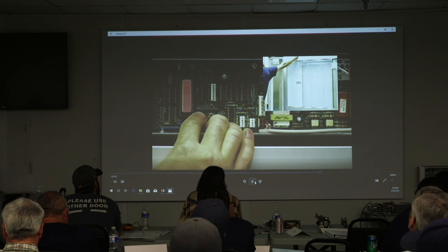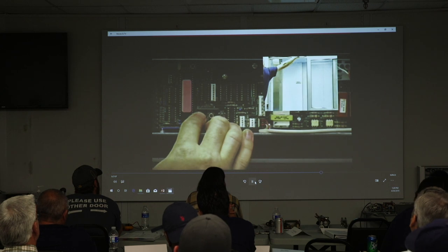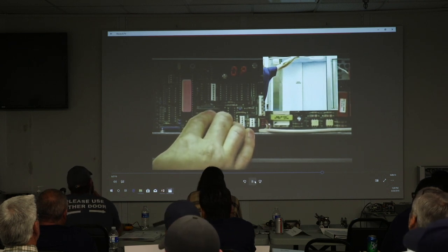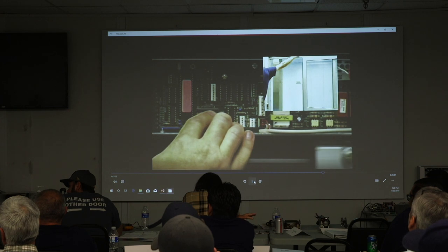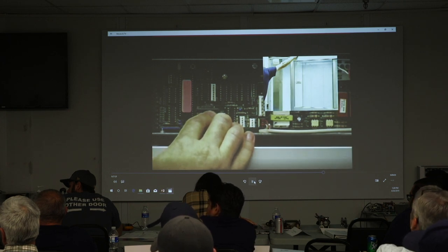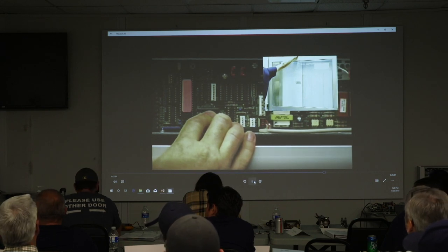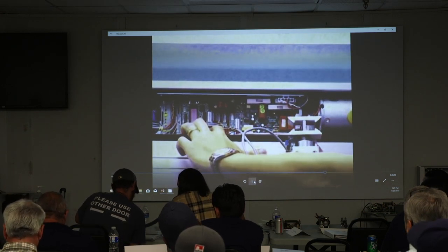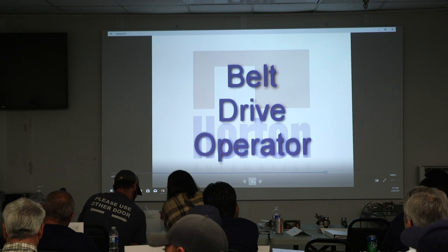Pressing up and down alternately will cause the door to open and close while displaying door position. This tests motor function as well as micro switch display. And how do you get to that function again? Up and down together. Set and down. The way I remember it is what you would do if you were doing a reset or going to the diagnostic. So setting down together, when you press and release reset, it takes you to function test. Okay. Pressing the set button will cycle the lock. That's in the book too, towards the back. Press reset to return to normal operation. The set button also allows you to test the lock.